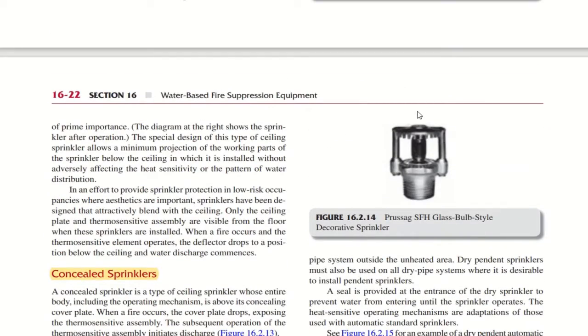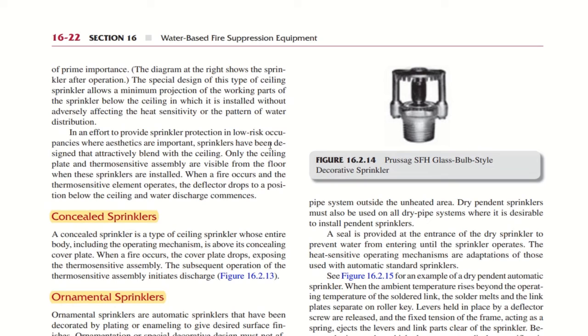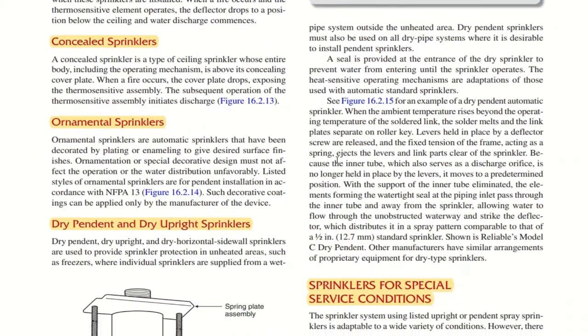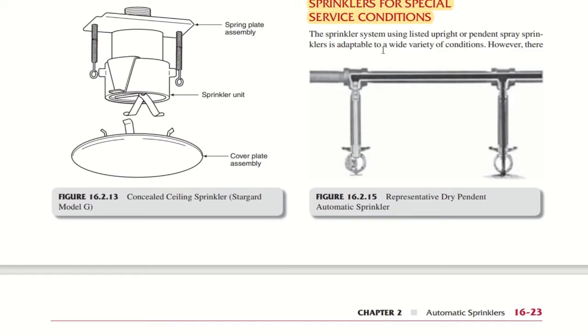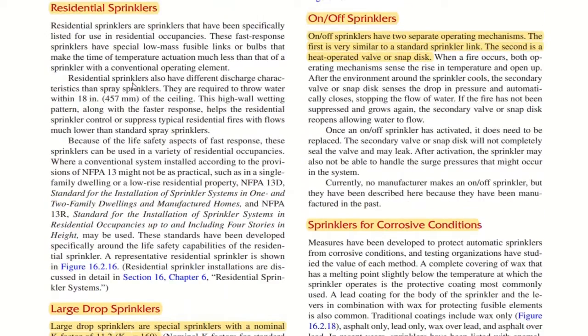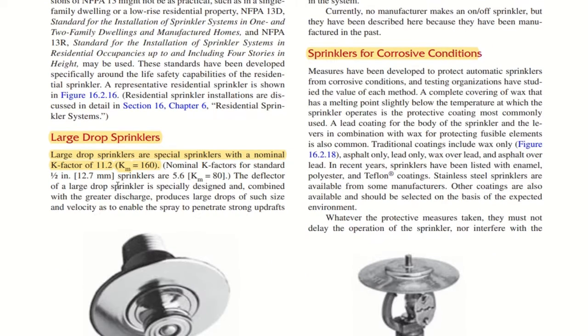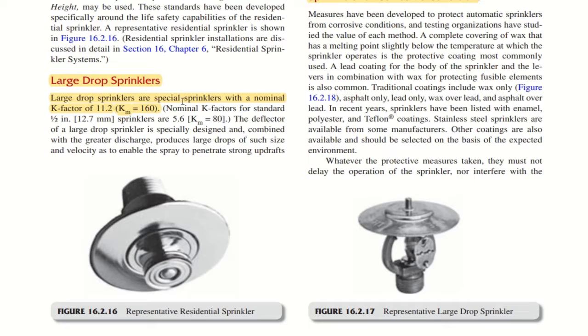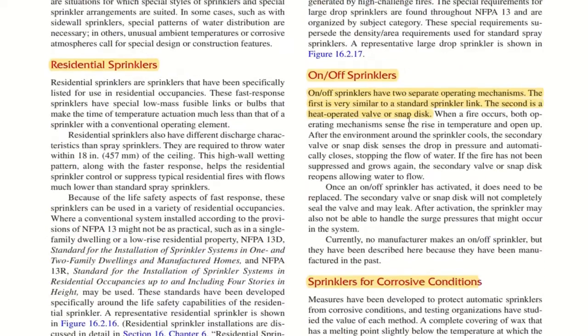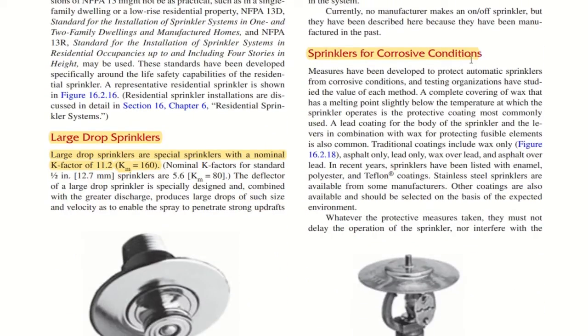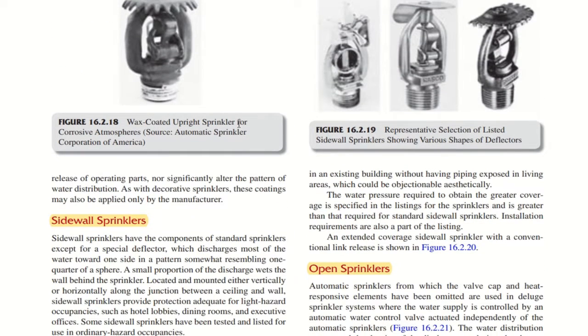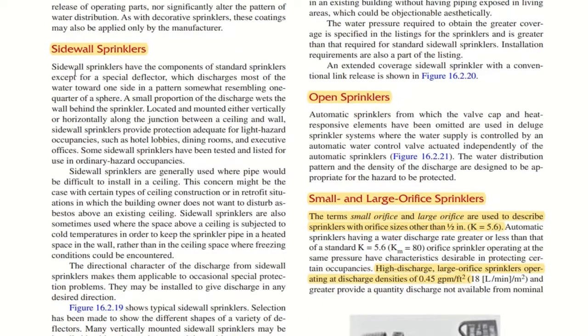So basically automatic sprinklers, this is chapter 2, automatic sprinklers. It covers the types of sprinklers as well. Apart from that, it also covers the most important table about the temperature ratings. So this you need to remember. Sprinklers for special service conditions, residential sprinklers, you can also find some points here. Large drop sprinklers with different types of K factors. Large drop sprinklers are special sprinklers with a nominal K factor of 11.2, or we can say K factor as 160. So you just need to remember that. On-off sprinklers are also there, apart from the sprinklers for corrosive conditions. And here you are getting an idea, I believe, that all these are covered in the automatic sprinkler chapter.